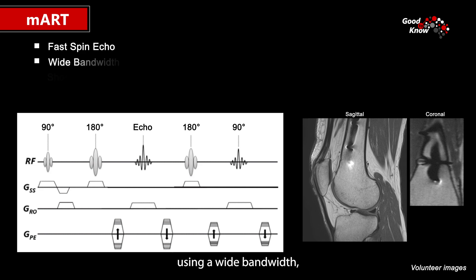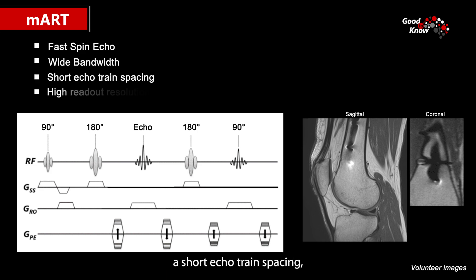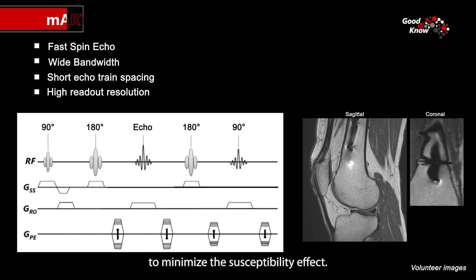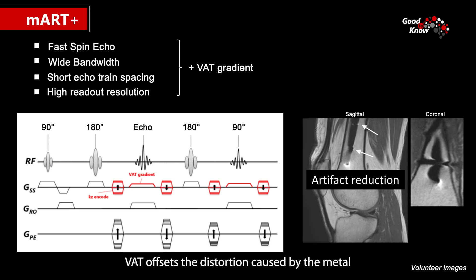The first one is called mART and is based on a fast spin echo sequence using a wide bandwidth, a short echo-spacing, and a high readout resolution to minimize the susceptibility effect. The second approach is called mART+, which combines this fast spin echo sequence with an additional gradient on the slice called View Angle Tilting or VAT. VAT offsets the distortion caused by the metal in the readout direction, further reducing metal artifacts in the plane.